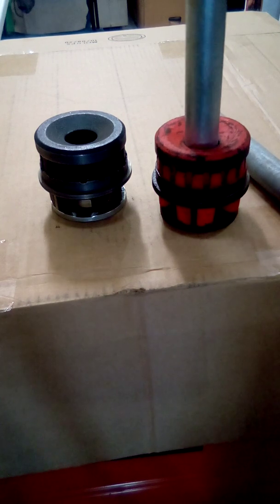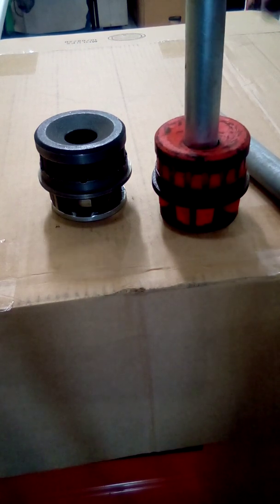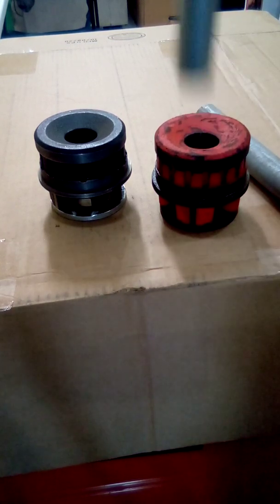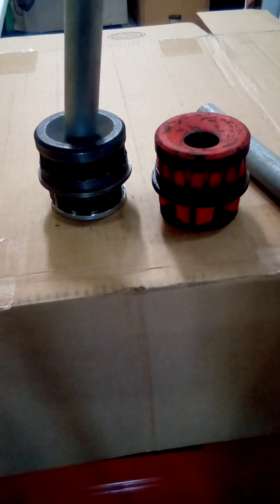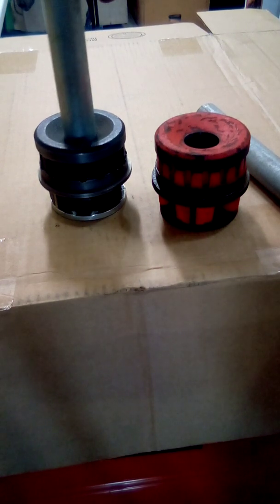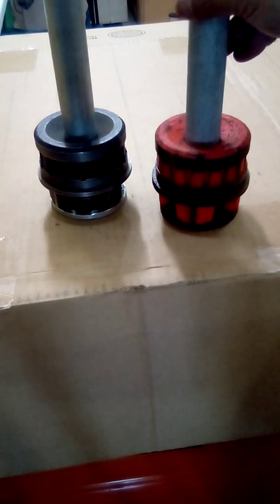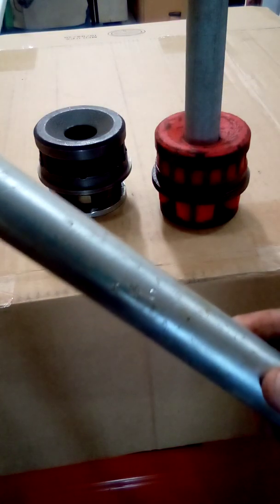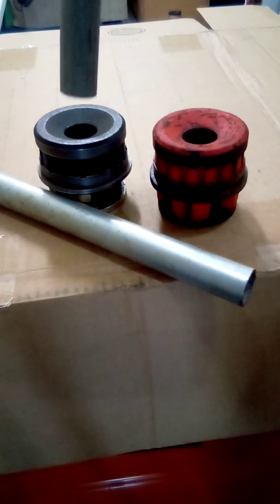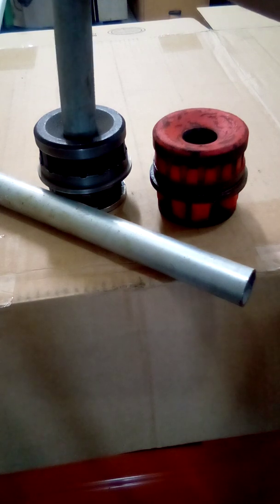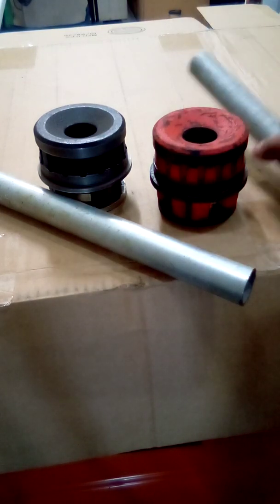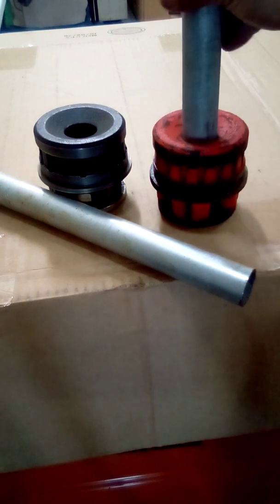So you can see the play right here, how much play's in it. This is the IMC conduit, and then if you stick it into the IMC die, no play, okay. Here's the rigid play, but that's what it's meant for. Now let me take this out. This is the IMC, IMC, and stick the rigid in here. Watch this. It doesn't fit, okay.